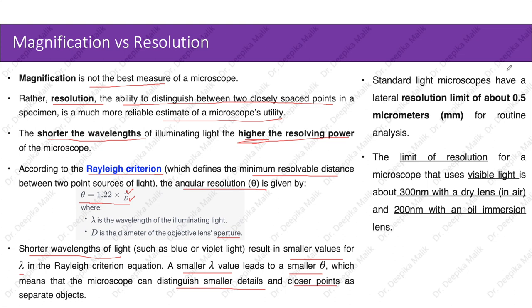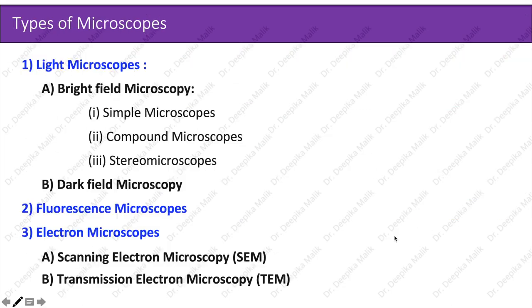Standard light microscopes have a lateral resolution limit of about 0.5 micrometers for routine analysis. The limit of resolution for a microscope that uses visible light is about 300 nanometers with a dry lens in air, and 200 nanometers with an immersion lens.